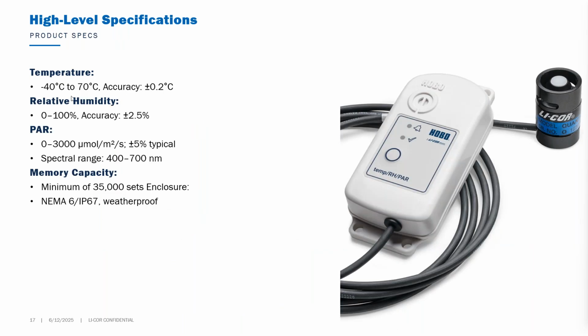So, all right, a little bit more about the spec. Again, the temperature and relative humidity spec, pretty standard to generally what we do. So temperature is at 0.2 degrees C, relative humidity plus minus 2.5%. The range for PAR is from 0 to 3,000 micromoles per meter square per second, and about plus minus 5% typical. And I'll touch on the accuracy part. When it comes to the memory, you'll get a minimum of 35,000 sets. And by that, what I mean, depending on the number of channels you have enabled, let's say if you have all channels enabled, you'll have a minimum of 35,000 data sets. And if you disable half of them, then you'll double it up, but I think it's a max of about 200,000 data sets that you'll get.